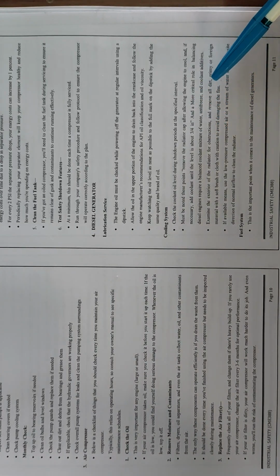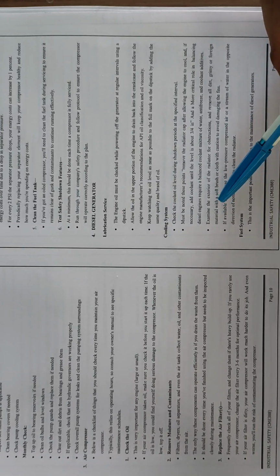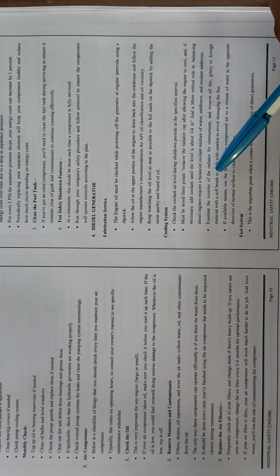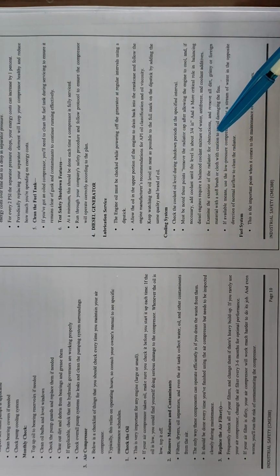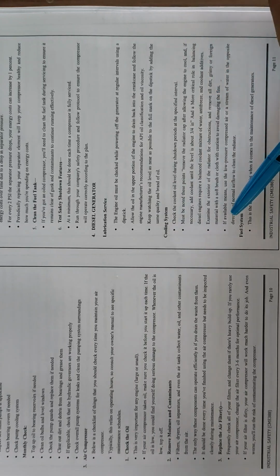Examine the exterior of the radiator for obstructions and remove all dirt, grime, and foreign material with a soft brush or cloth, with caution to avoid damaging the fins. If available, use low pressure compressed air or a stream of water in the opposite direction of normal airflow to clean the radiator.